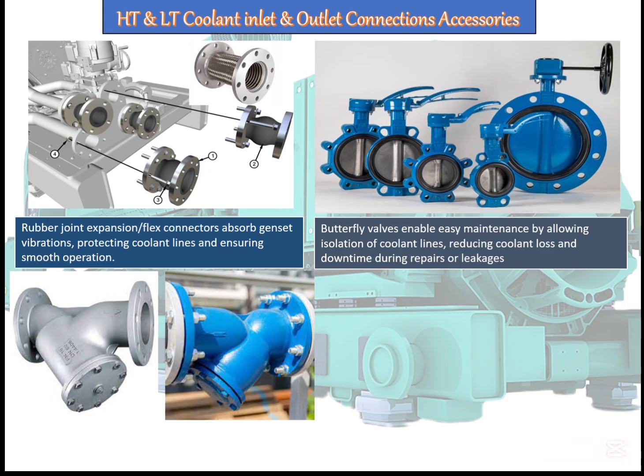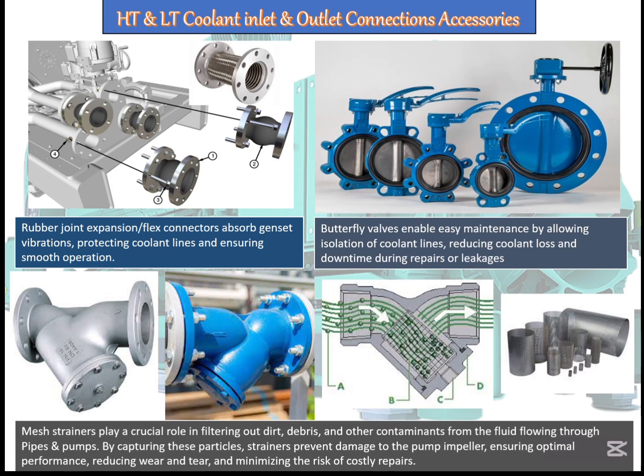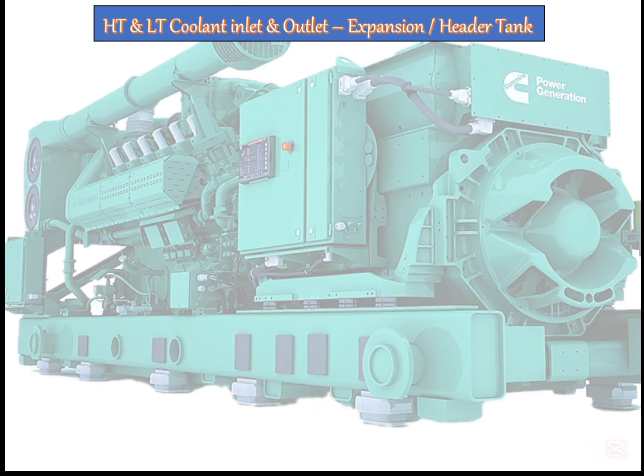Then it's equally better to use strainers on the incoming lines. By the time the pipes grow old, they will introduce corrosion and other particles. When the coolant is flowing, it will go to your pump. So it's better, before sending it to the circulation pump, to separate all the particles, and for that purpose we can use a strainer, so that all the debris or dust will stay in the strainer and the clean water will pass through the pump. That will not damage the pump impellers and others. So that is another advantage of using the strainer.